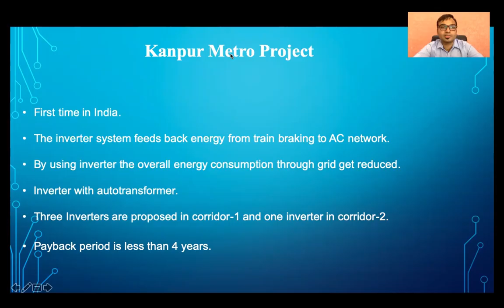Kanpur Metro project will be the first metro in India on a DC traction system which is using inverter technology for recuperation of regenerative energy. The inverter will definitely reduce the overall energy consumption through the grid. We'll be using inverters with auto transformers, and initially we are proposing 3 inverters in corridor 1 and 1 inverter in corridor 2. As per the simulation results, the payback period is less than 4 years.